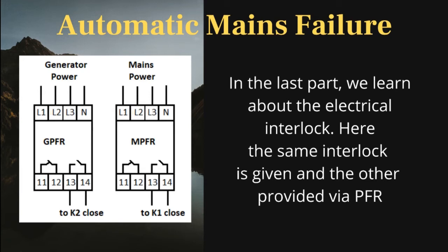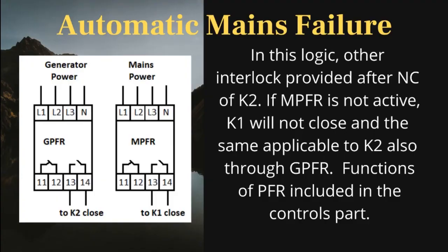In the last part, we learned about the electrical interlock. Here the same interlock is given, with the other interlock provided via PFR. In this logic, the other interlock is provided after the NC contact of K2. If MPFR is not active, K1 will not close, and the same applies to K2 through GPFR. Functions of PFR are included in the controls part.